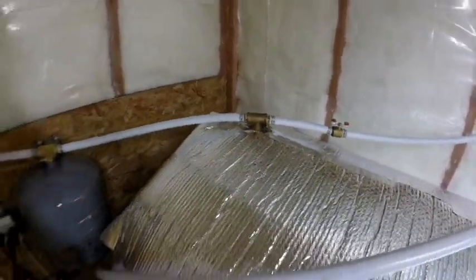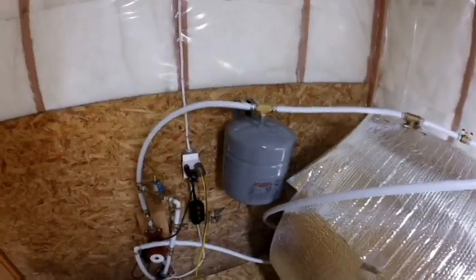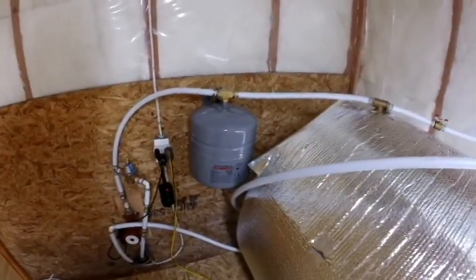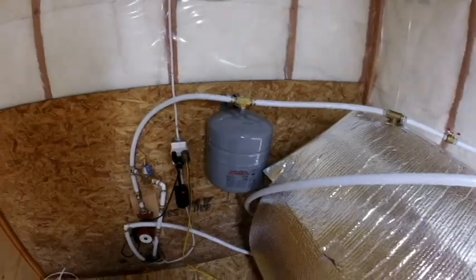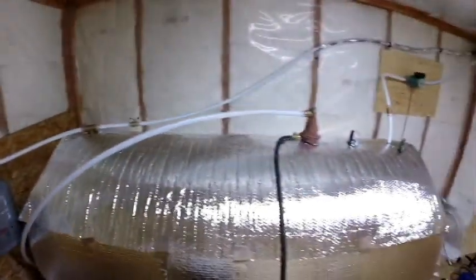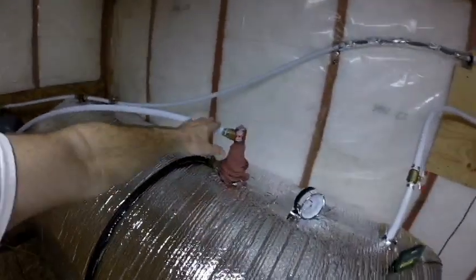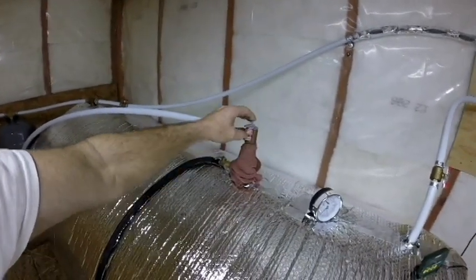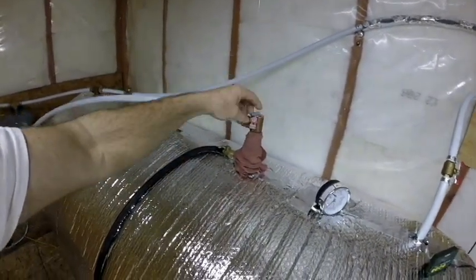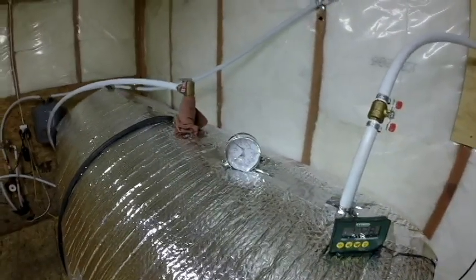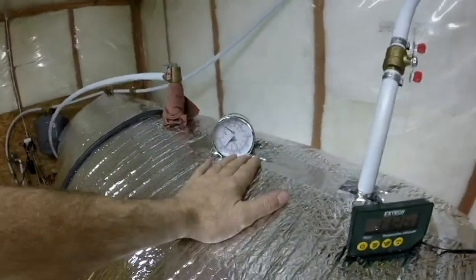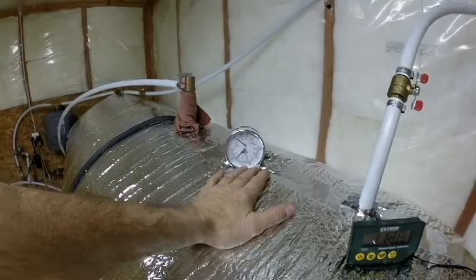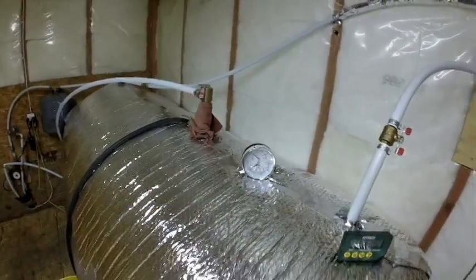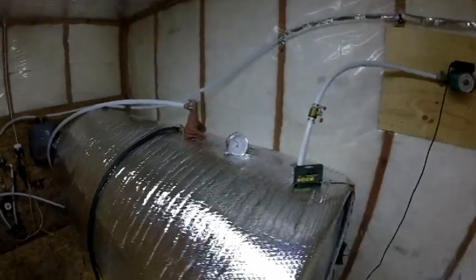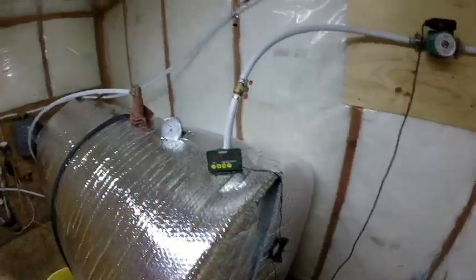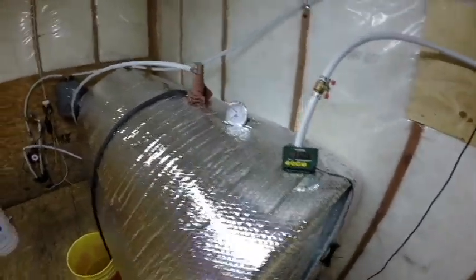I also have my expansion tank in there, which is necessary for a boiler system, because as the water expands and contracts, if you don't have that, then the water will constantly be blowing off on the thermal relief valve, or pressure relief valve as you have it. It does both. I have a pressure temperature gauge in there. As you can see, the water right now is only at 130 degrees at 15 psi, so I just lit this thing. It's warming up. The water at the bottom of the tank is at 113 degrees Fahrenheit.